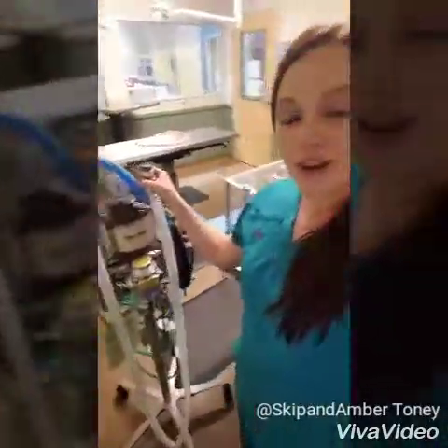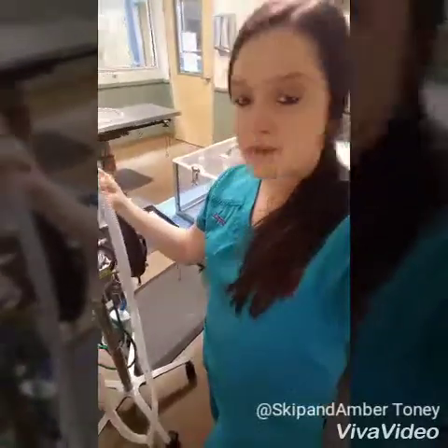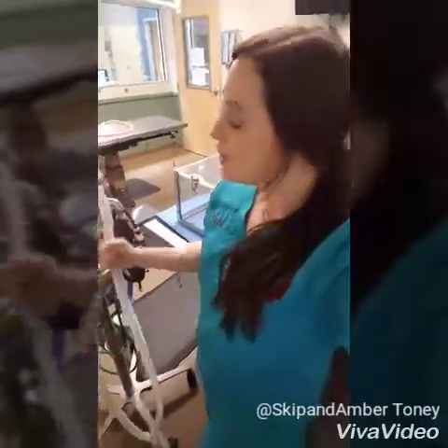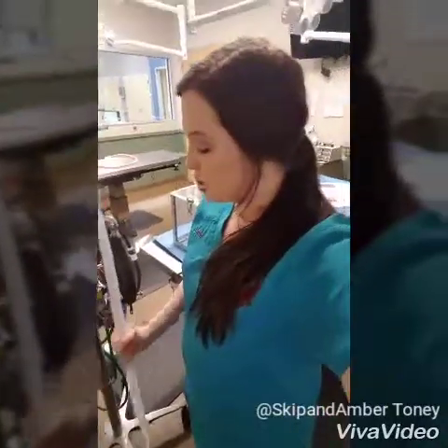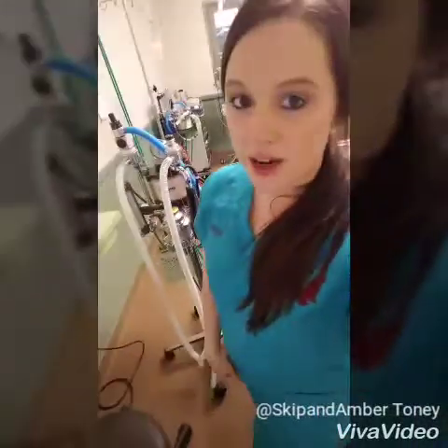Okay, I'm now going to demonstrate the parts of our anesthetic machine right here. We have a rebreathing machine. We do not have a non-rebreathing machine, which is what you would typically use in any animal weighing less than 7 kilograms. It's easier for their body to handle because of the low gas resistance, but we do not have one. We definitely are going to invest in one very shortly. We just don't have one at this time.